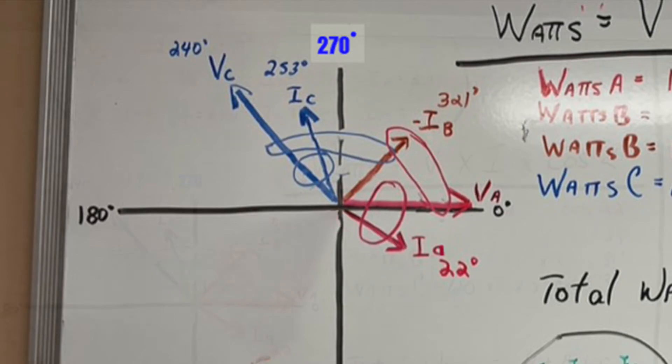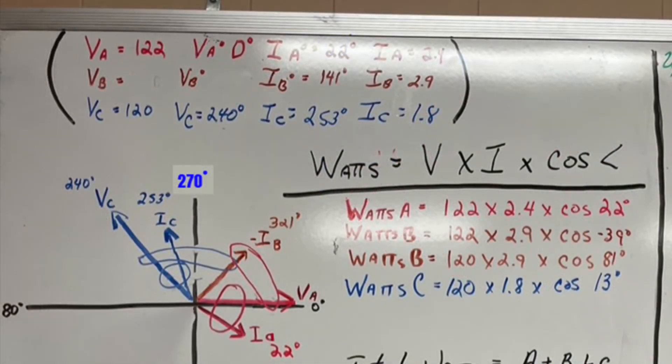Okay, now we're going to go ahead and figure out the watts for this. And what we're going to do is we're going to go ahead and circle VA to current A and we'll have 122 volts times 2.4 times cosine of 22 degrees. So that tells me the watts for phase A.